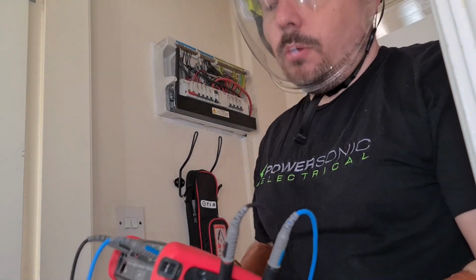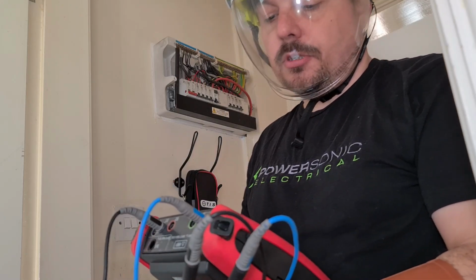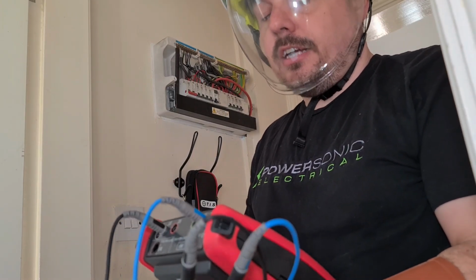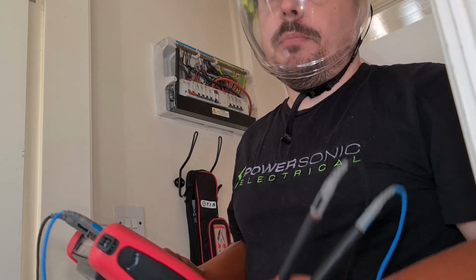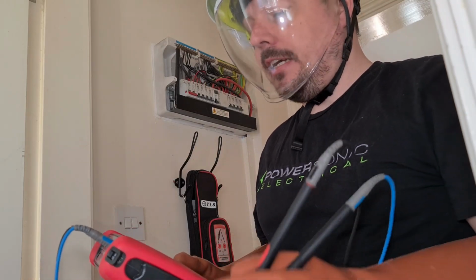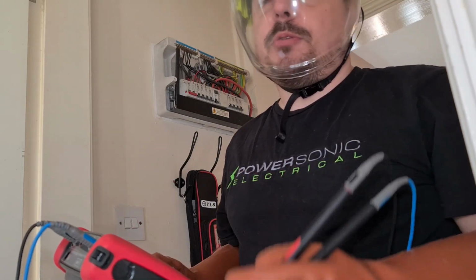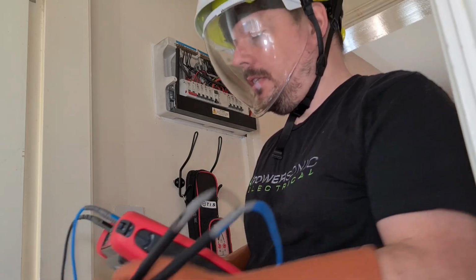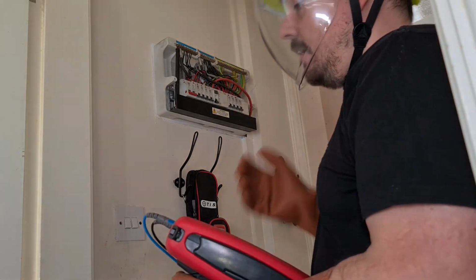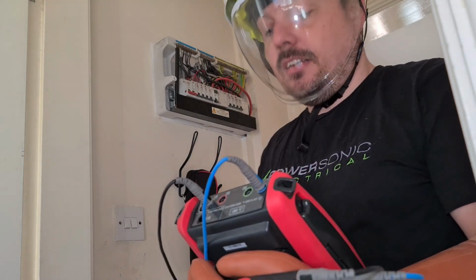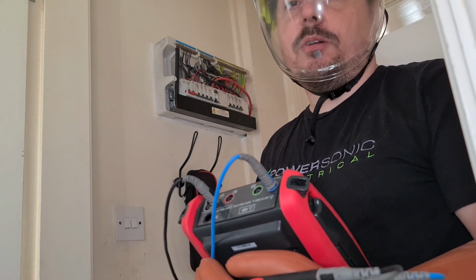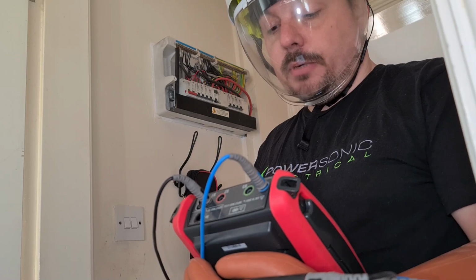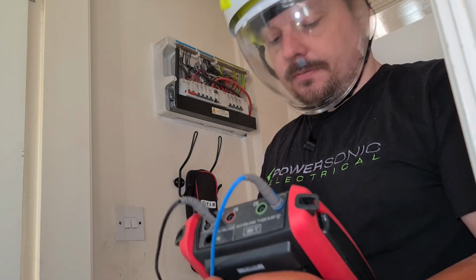So we've measured 1.28 kA on the prospective fault current there. The actual Z value is very similar, so that's the impedance between the line and neutral. We are getting a little bit higher on the prospective fault current, that's because the bonds are connected basically. But yeah, I can now put this back together and carry on with some of the testing. Make sure we've got a good isolation in place.